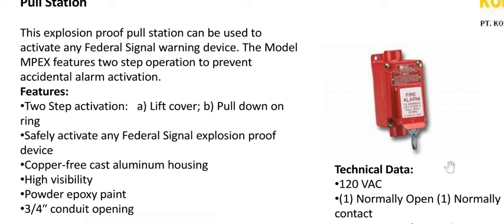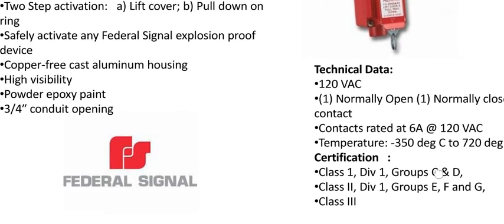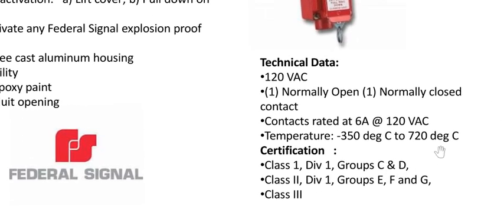Copper-free cast aluminium housing, high visibility powder epoxy paint, 3/4 inch conduit opening. Technical data: 120 volt alternating current. Normally open, normally closed contact. Contacts rated at 6 amperes and 120 volts alternating current. Temperature is minus 35 degrees Celsius to 72 degrees Celsius. Certification is Class 1 Div 1, Group C and D, Class 2 Div 1, Group E, F and G, and Class 3.